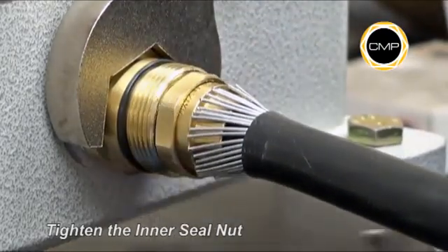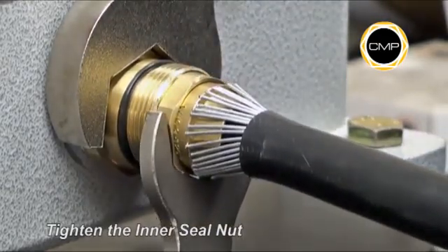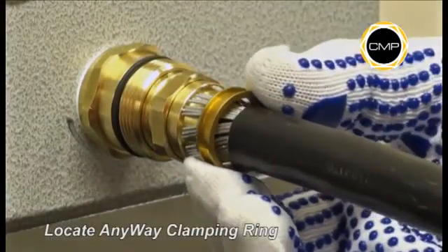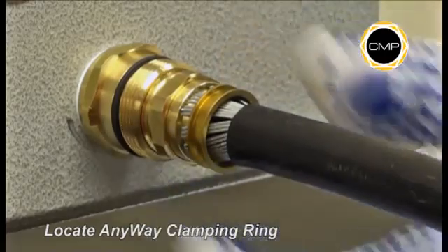Hold the entry component with a spanner and tighten the inner seal nut until the two components are metal to metal and cannot be tightened any further. Locate the AnyWay clamping ring onto the armour cone. Ensure the braid is in 360-degree contact with both the cone and the any-way ring.